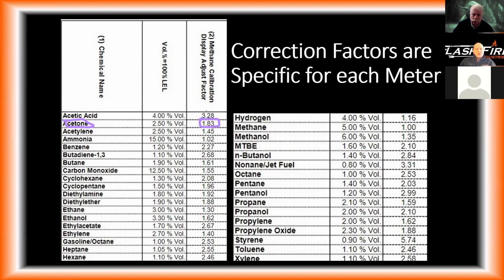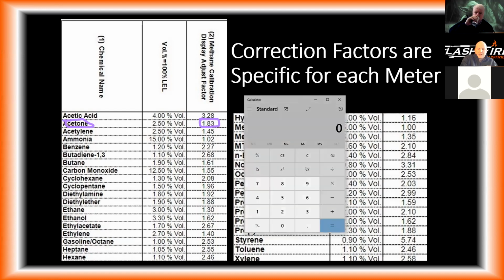So if we were to do the correction factor for this, pull up the calculator. And you're not going to pull up a calculator on scene, and that's why I show you those 2 and 3 type things. Let's say my meter was reading 10% LEL. I just take the 10 and multiply it by 1.83, and my meter is actually showing 18.3% LEL.